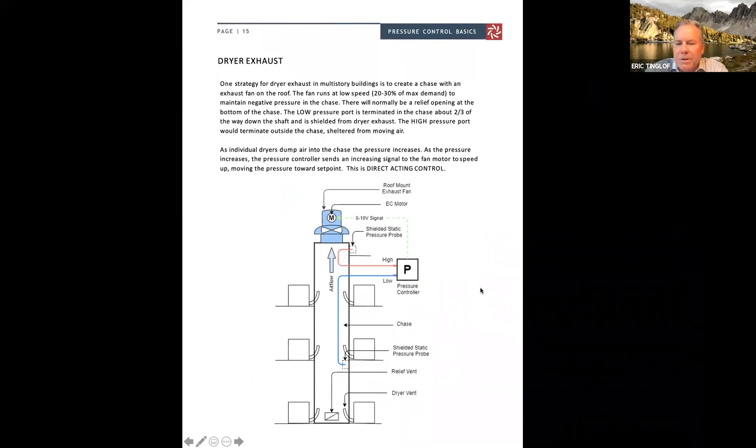Dryer exhaust in multi-story buildings in a lot of markets these days for condominiums, apartments, hotels. You have a common chase, multiple floors, dryer exhaust from each unit pushing that air into a negatively pressurized chase. So one fan up on the top of the chase, and then you have your low pressure about two thirds of the way down the chase to pick up the static pressure. And then on the high side, you have this to atmosphere on the outside of the chase. As the pressure goes up in this chase because you have more units coming on, that will send a signal back to the pressure controller to the EC motor to speed up. So that becomes now a direct acting scenario.